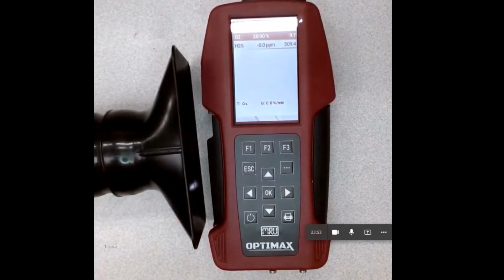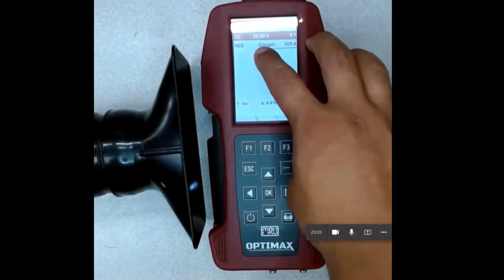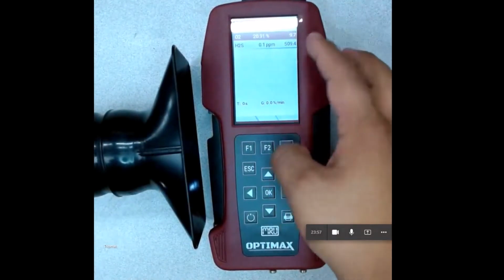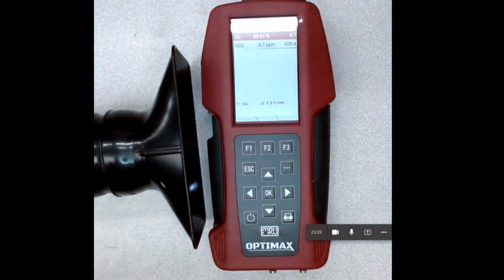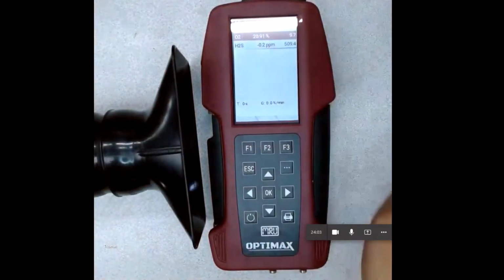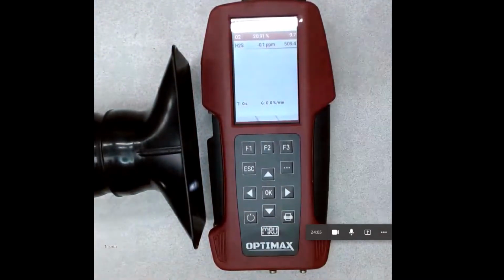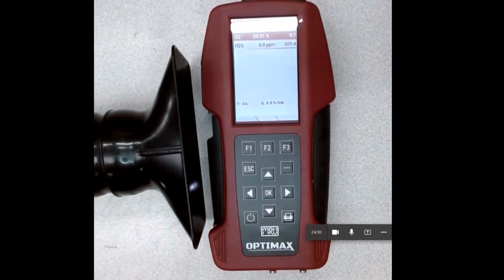So from here, one thing that we'll just confirm, the oxygen value looks really good for us, because it's reading fresh air, so it should be around 21%. And H2S is reading essentially 0. So we'll start sampling gas. So those are the nominal values. So this is the nominal value adjustment.